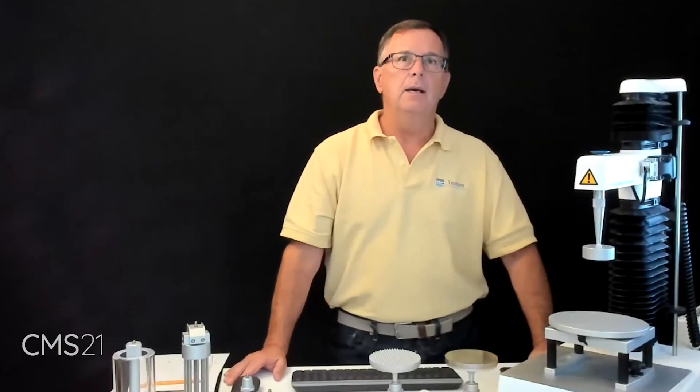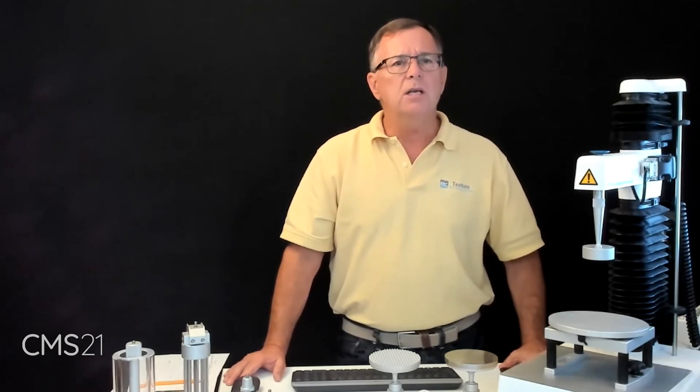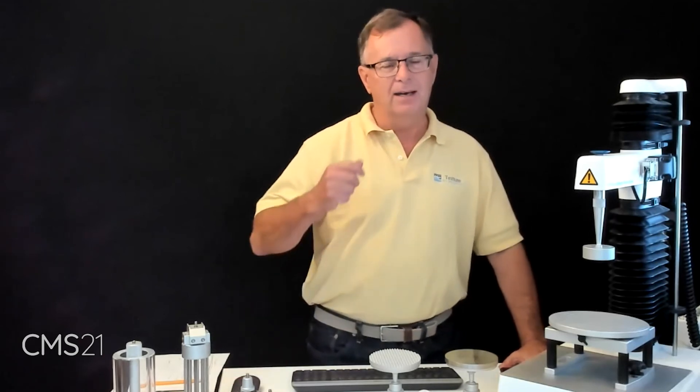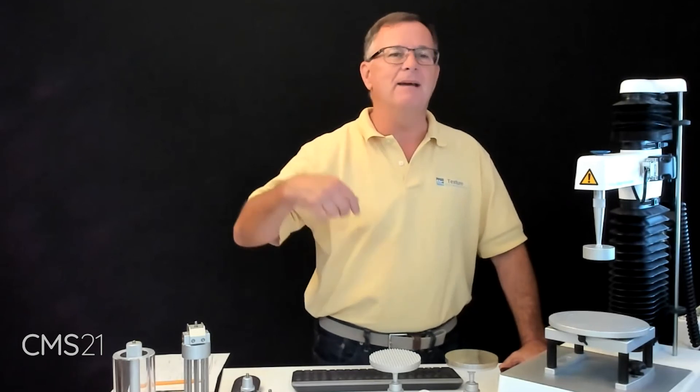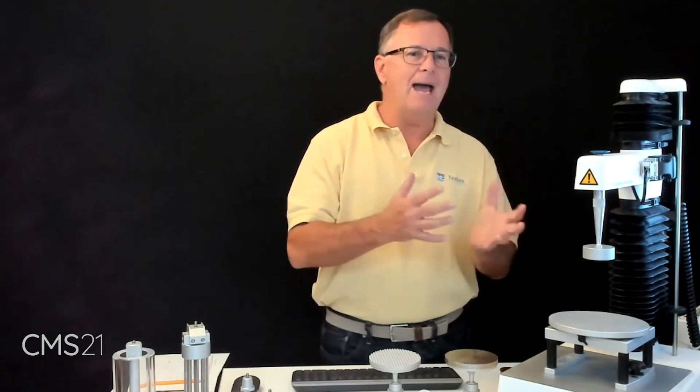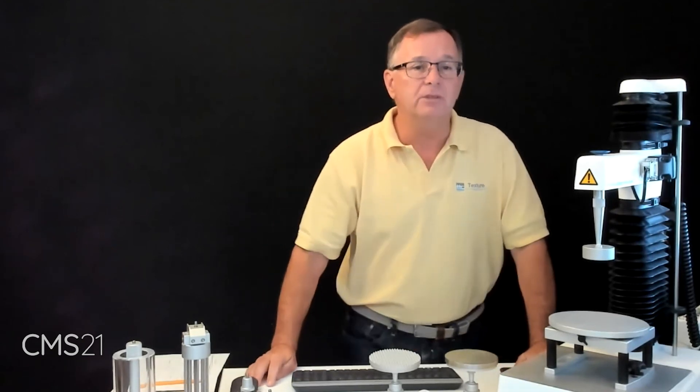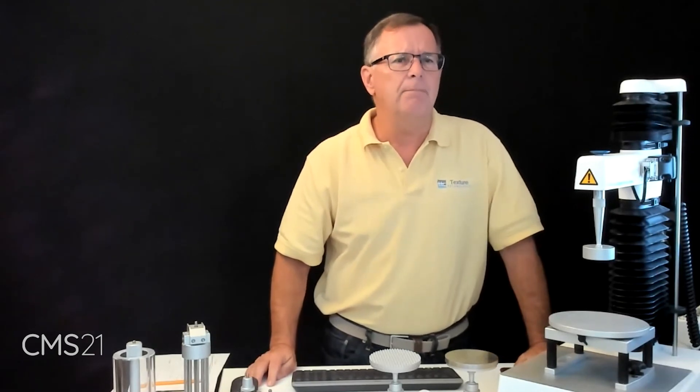A couple more things that come to mind - if there was a team that wanted to create their own custom fixture, is that something they would be able to do or would they need to work with your team to do that? They do that all the time. Usually we'll give them a little bit of guidance - you want to have a metric 3 thread going up into the base and a metric 6 thread going up into the load cell. You want to have something centered, you want to not have too much mass. If the material they're doing is something like a gel, you want to have a very light probe so that it doesn't have a lot of mass and acceleration when this thing's bouncing all over the place. So we'll give them some guidance, but they design their own probes and make it.